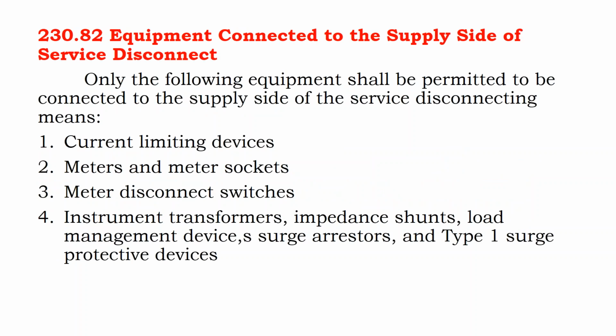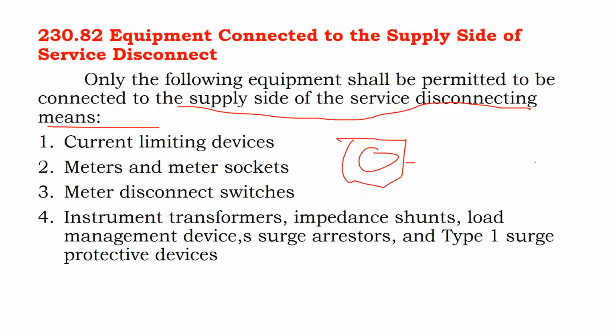It says only the following equipment shall be permitted to be connected to the supply side of the service disconnecting means. What does this supply side of the service disconnecting means actually mean? Well, we have our utility meter, and then we have our main service panel with our breakers. And then you have your main breaker on your main service panel. This main breaker is the service disconnecting means.